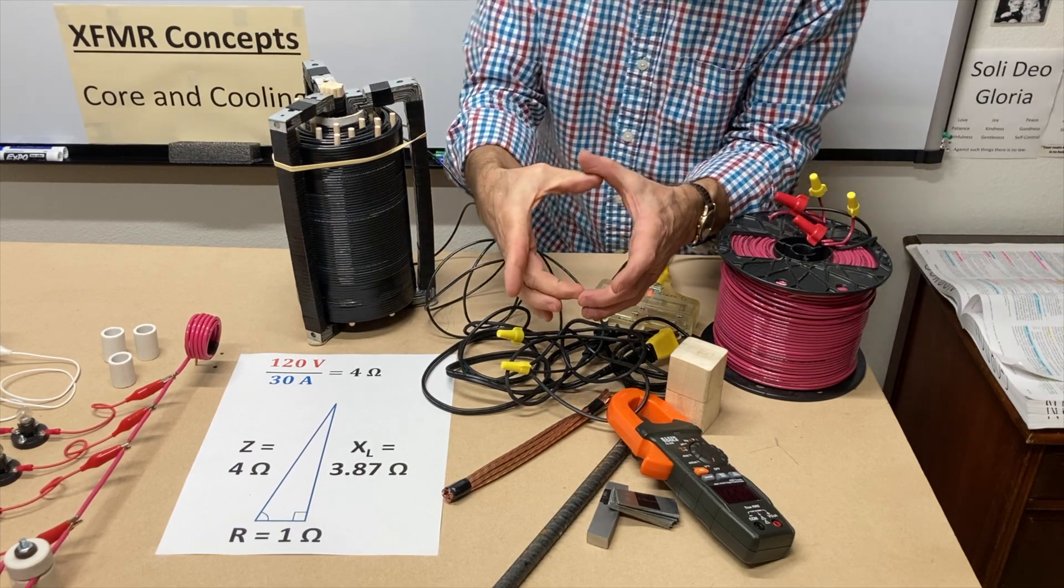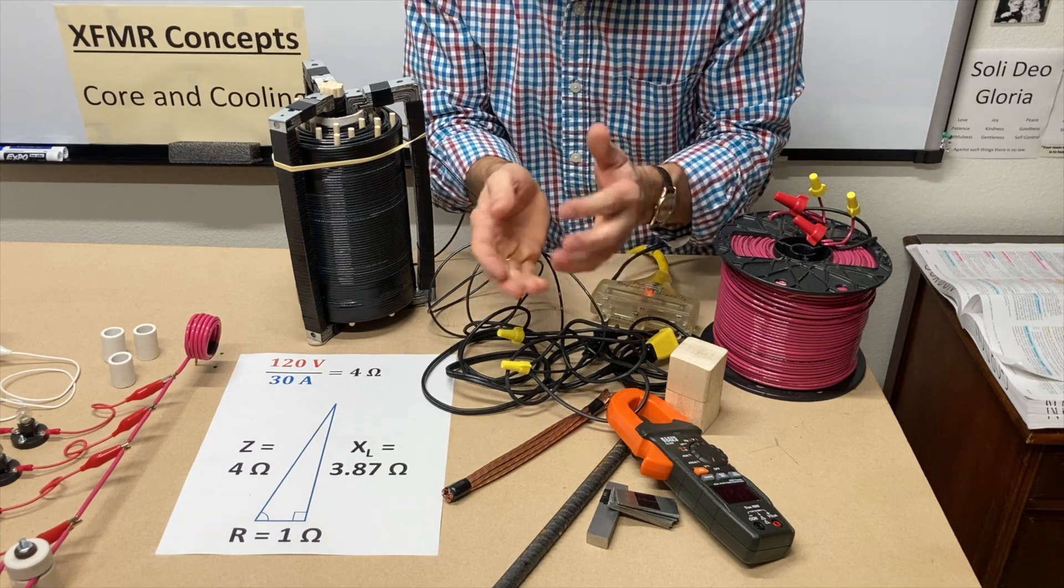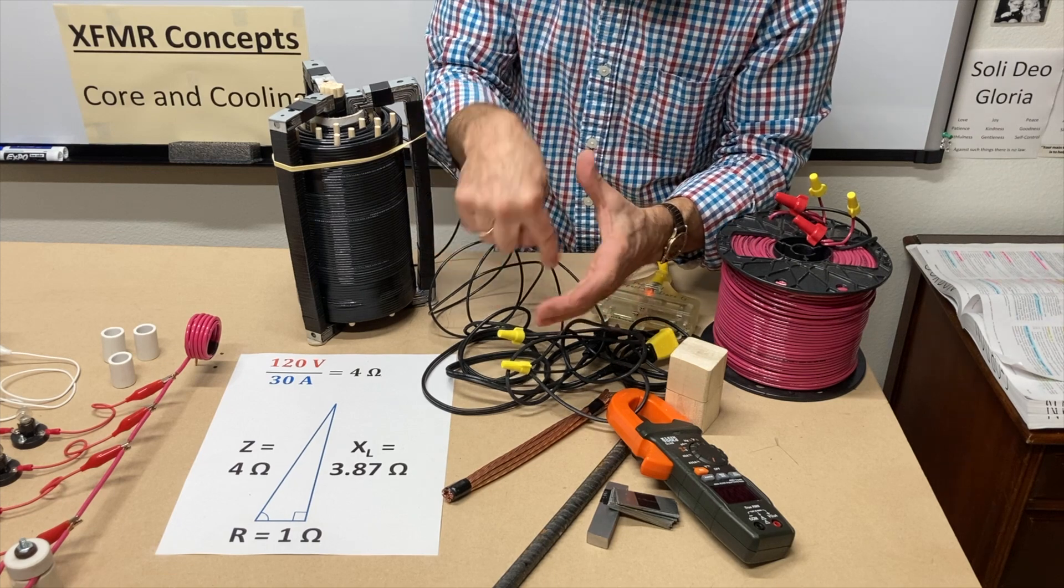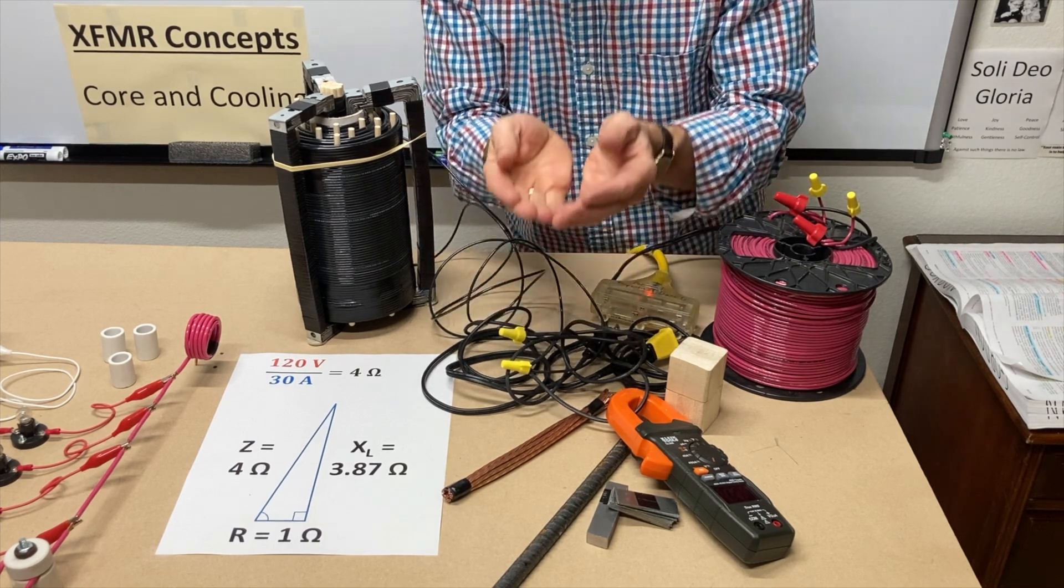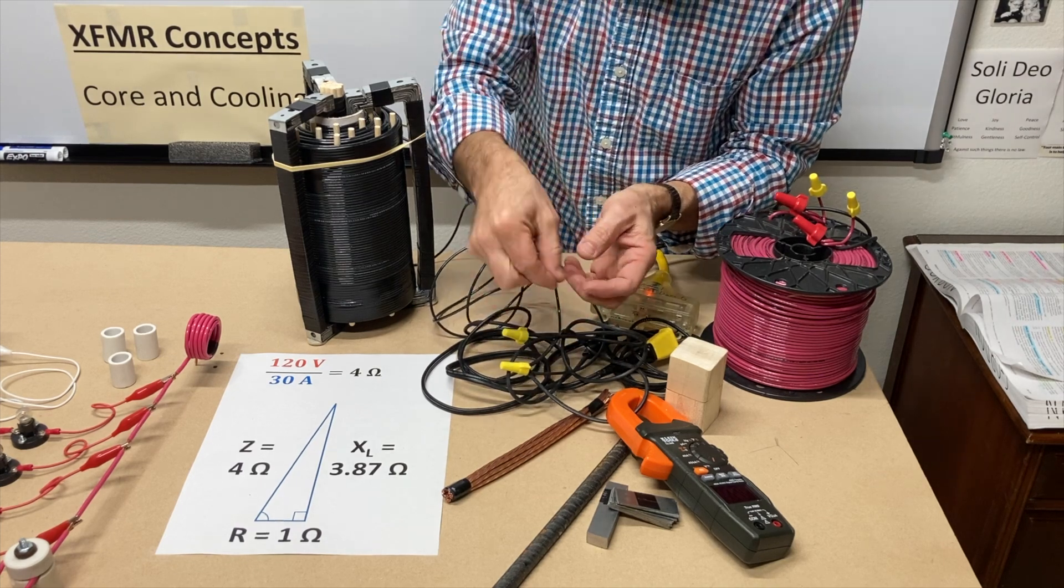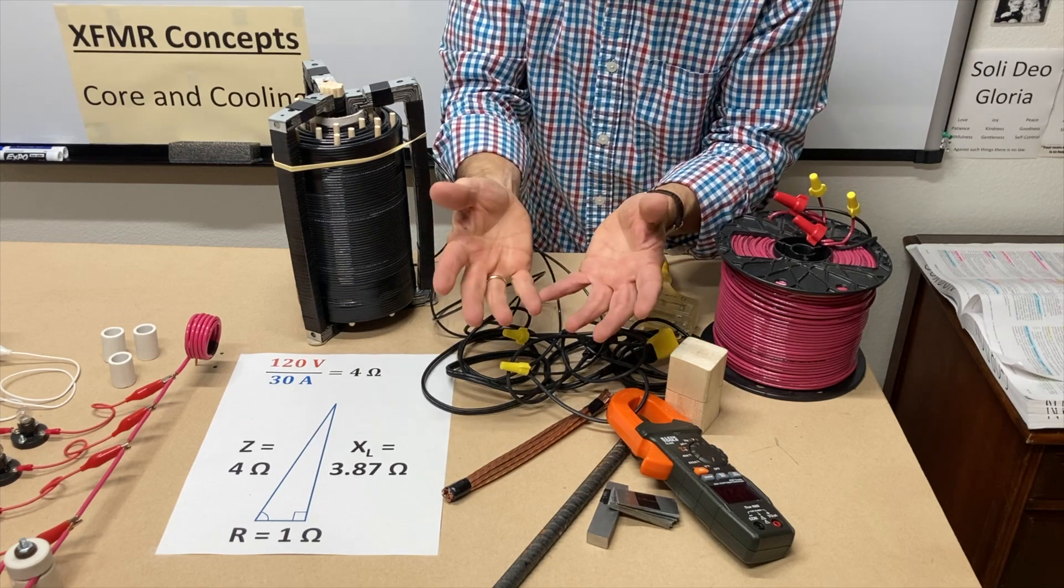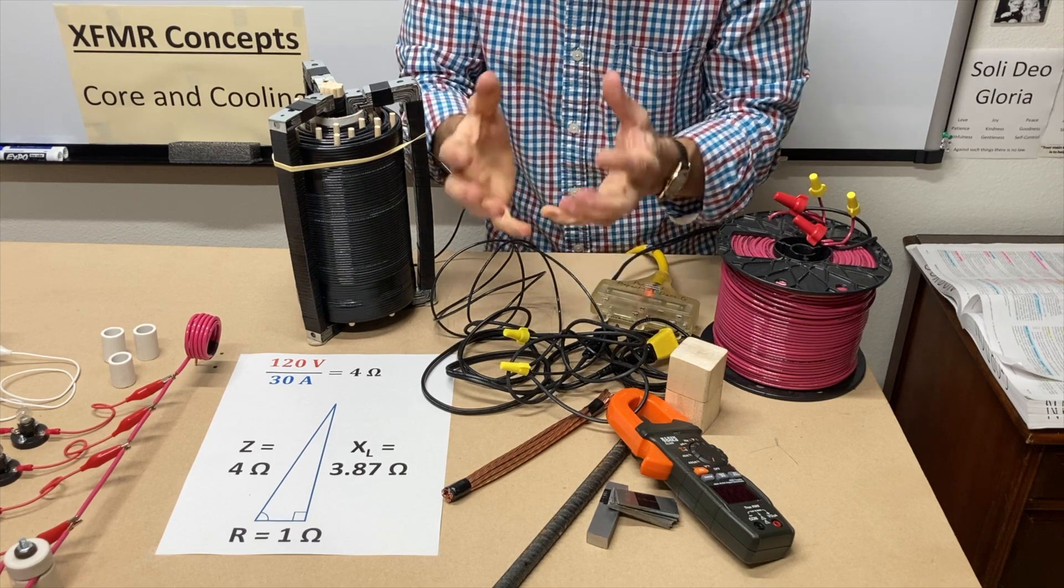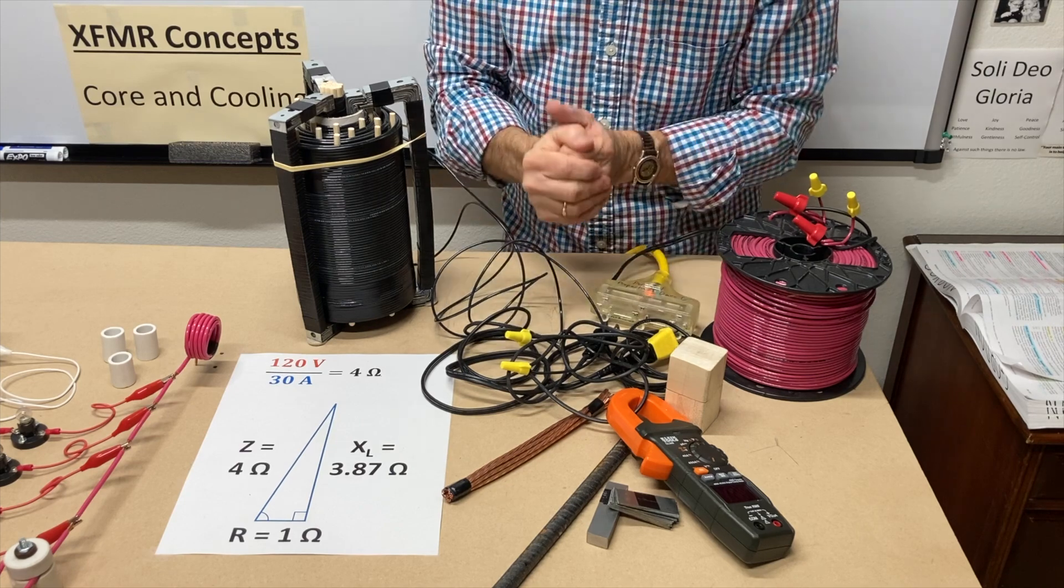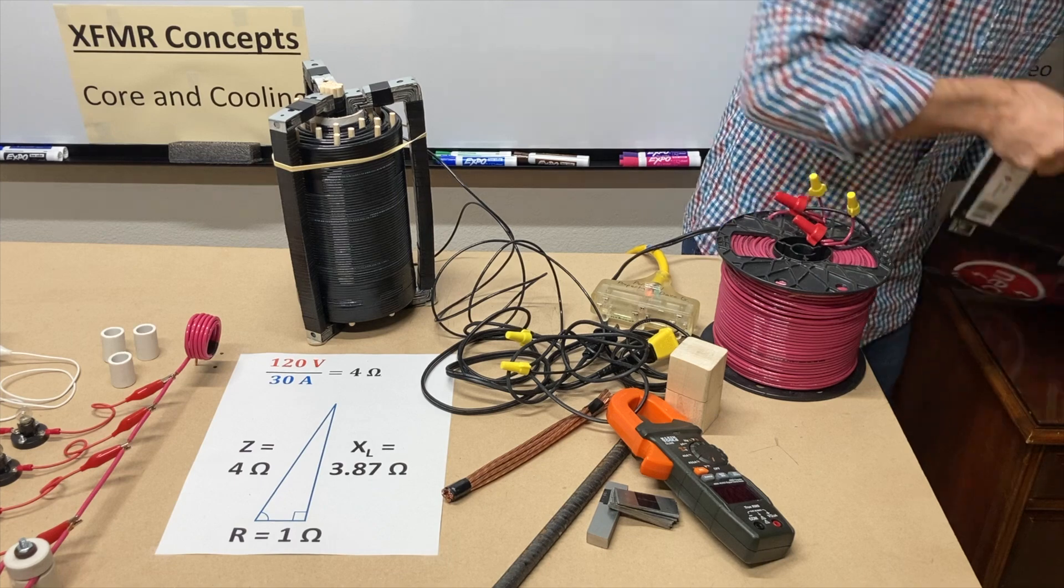But you say, well, what about the transformers? I've seen them where the wire is just wrapped tight around the core. Well, there the engineers have calculated out how much current they expect to be flowing in that wire. What the temperature rise, right? How much hotter will it get? And can the wire, its insulation and the core handle that temperature? Sure. That's what they calculate out. So if you use it beyond its rating, then you're going to start overheating any transformer.